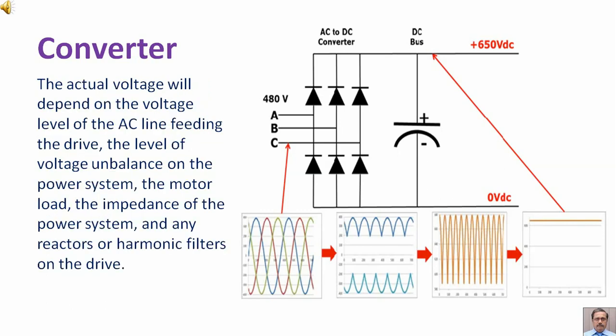The actual voltage will depend on the voltage level of the AC line feeding the drive, the level of voltage unbalance on the power system, the motor load, the impedance of the power system, and any reactors or harmonic filters on the drive.